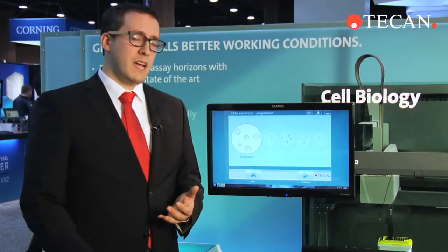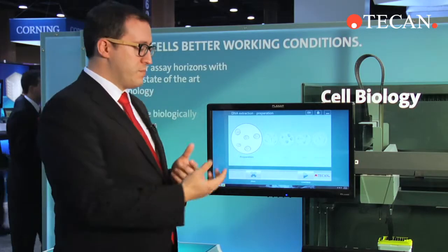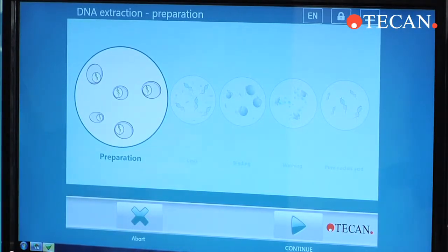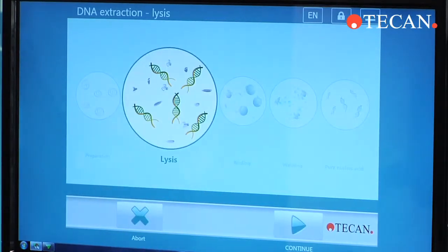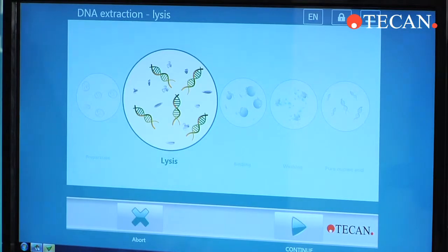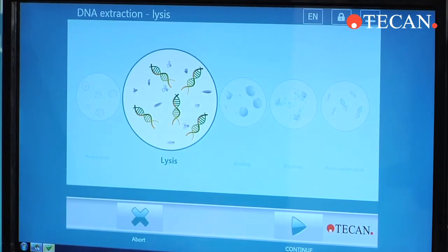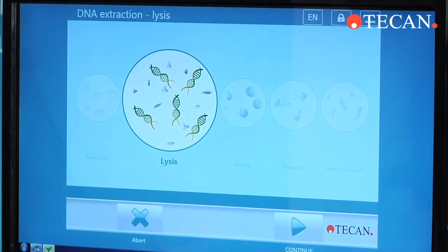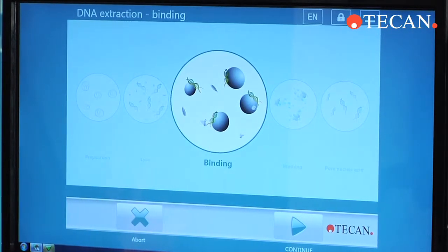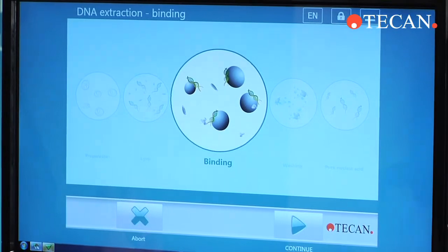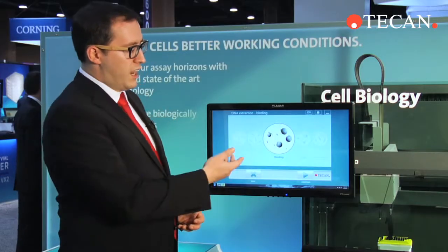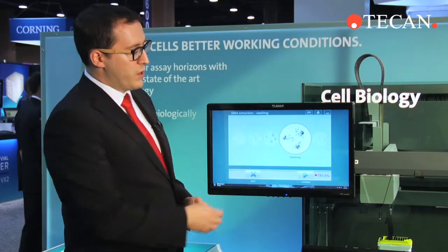During runtime we can also put up custom run information so that instead of just the standard scroll bar scrolling, if you want to show a picture that says something like sample distribution or incubation to really let the operator know what's happening, again in the words of the assay that they already understand, you can do that.